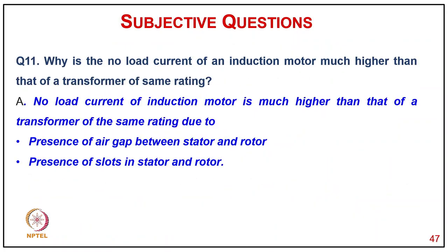Question number 11, what is the no load current of an induction motor? Why is the no load current of an induction motor higher than that of a transformer of the same rating? The answer is, the no load current of an induction motor is much higher than that of a transformer due to the presence of an air gap between the stator and rotor and the presence of slots in the stator and rotor.